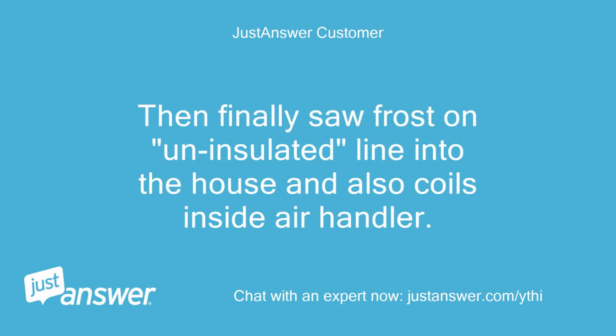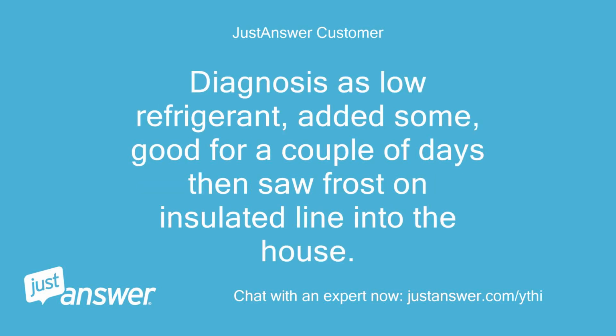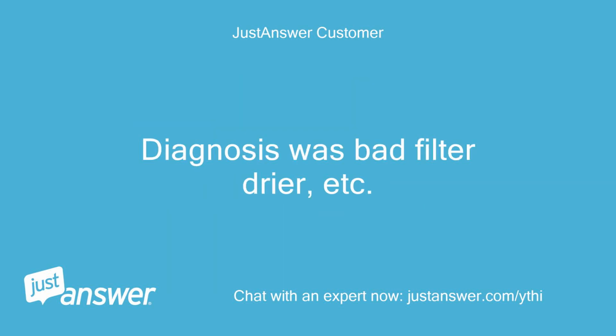Then finally saw frost on un-insulated line into the house and also coils inside air handler. Diagnosis as low refrigerant, added some, good for a couple of days, then saw frost on insulated line into the house. Diagnosis was bad filter dryer, etc.